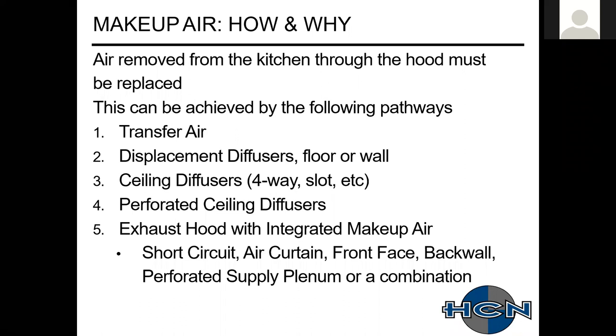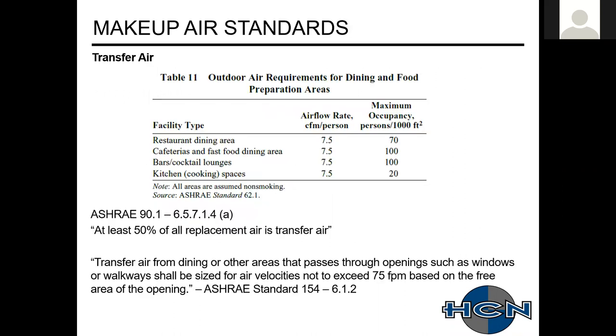For most designs, everyone will see something like an 80-20 design. In reality, we'd like to use some of that transfer air, maybe even a little bit more, depending on the size of your restaurant or the facility you're trying to do. So transfer air: ASHRAE 62.1, pulling from the 2016 versions of all the ASHRAE codes that I'm going to talk about. You're designing for that ventilation for that space already. So you're already heating and cooling that air. Why wouldn't we want to use that air and transfer it over to the kitchen? And ASHRAE 90.1 and energy codes allow that. They actually want you to do that.